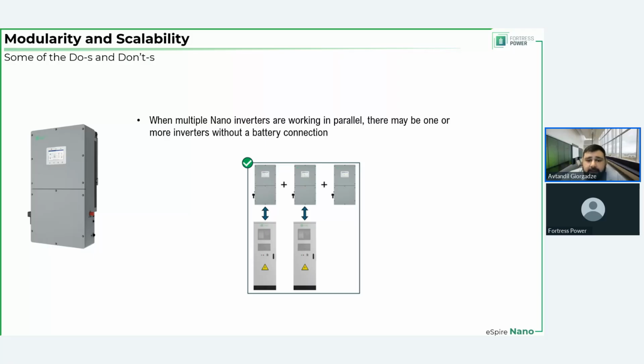Totally fine. Another thing is that you might decide that, well, yes, Fortress Power does allow me to have a Pro package in which I will have an AC-coupled PV inverter controlled by the other 2 inverters, but I think it's more useful for me to have 3 inverters, 2 of them with batteries and 1 of them without the battery, because what if, I don't know, 5 years down the road, I need more capacity, that type of thing. Case by case, people have different reasons why they want to do this or not do this, but it's always good to have this capability.